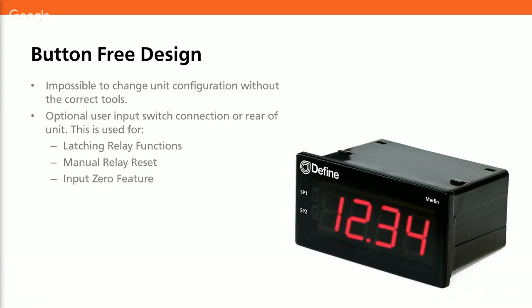The switch can also be used as a manual 0. When you enable this mode and press the button, the current input signal will be used as a reference point. The display then temporarily shows all measurements relative to the point when you pushed the 0. To get your head around that, a common example is the tare button on your kitchen scales, so that you can zero out the weight of a bowl before you pour things in onto the scales.